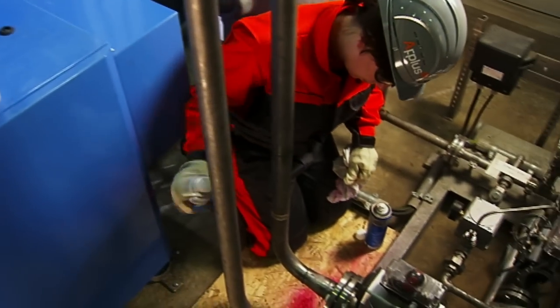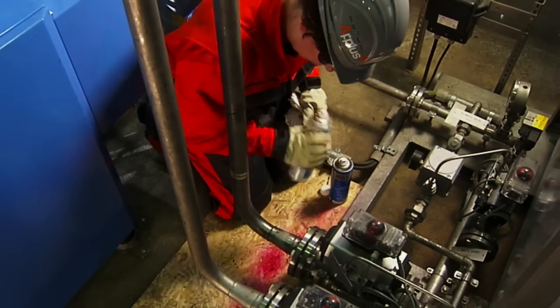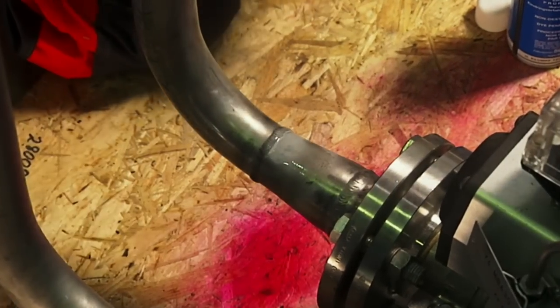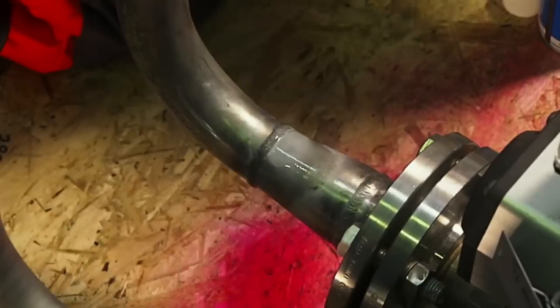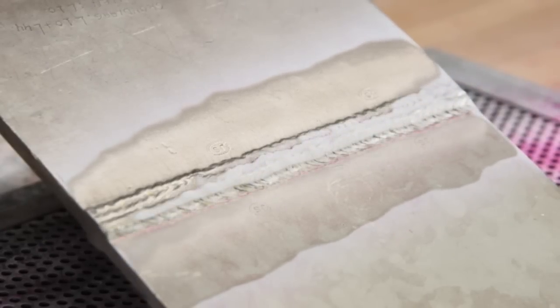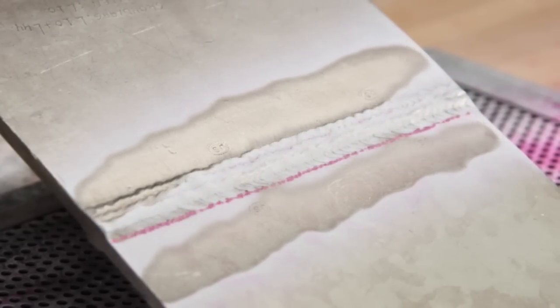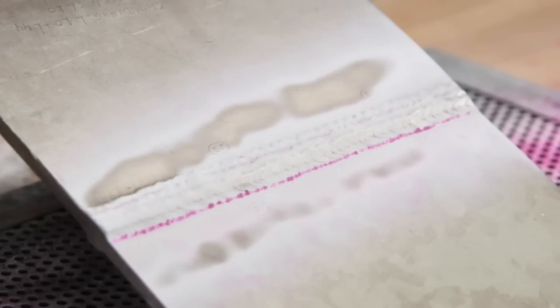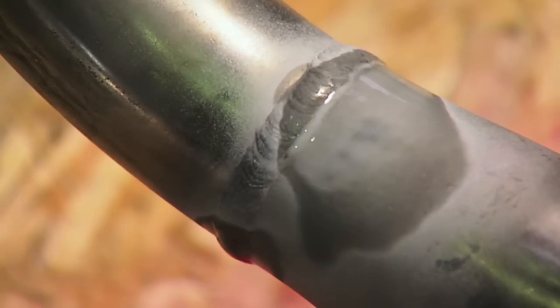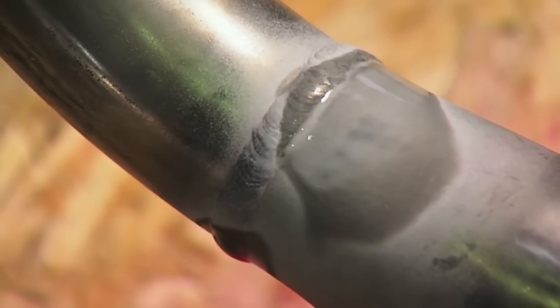A developer is applied with the third aerosol can. This forms a white chalk layer on the surface, making the hidden penetrating product visible. Here we see how the developer basically draws the penetrating product in sight. We call this the bleeding of the penetrating product. This shows us where there are any imperfections. In this case, no imperfections were found. The investigated part is unaffected.